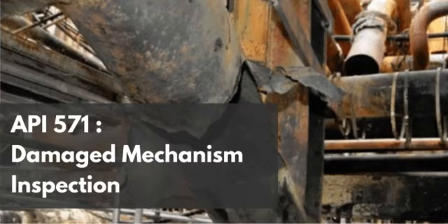But think about the logistics of this. We are talking about massive atmospheric storage tanks holding millions of gallons of liquid ammonia. How on earth do operators keep an asset that large perfectly, entirely oxygen-free? It's easily one of the most rigorous operational challenges in a chemical facility. You cannot simply empty an ammonia tank for inspection, open a hatch to the atmosphere, and then fill it back up. The moment atmospheric air fills that void, you have contaminated the system.